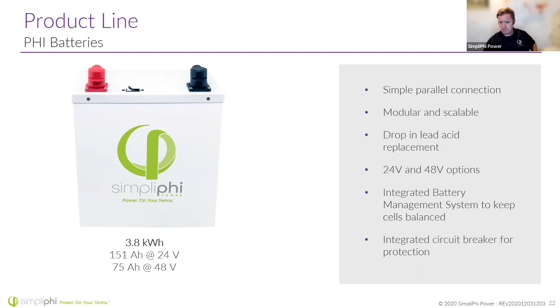They make a great drop-in lead acid replacement, you just have to disable that equalization stage. Like I mentioned, they come in 24 or 48 volts, and have that integrated battery management system. Really, that's the last line of defense. This battery management system is not an excuse for a poorly programmed or poorly sized system. You want to make sure you get that all dialed in, because it's going to protect the battery, but if you repeatedly go out of nominal conditions, it's not going to like that. We've also got that integrated circuit breaker in there.